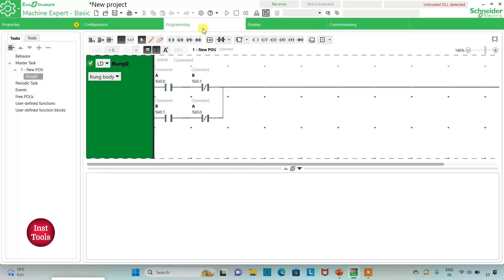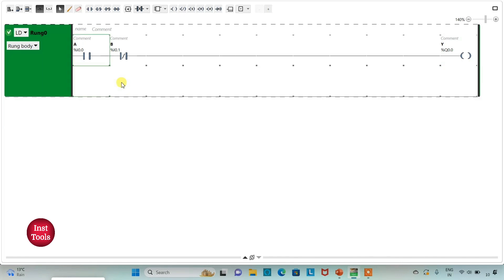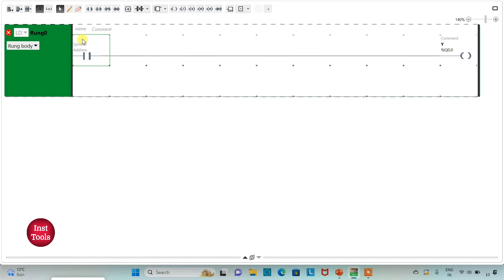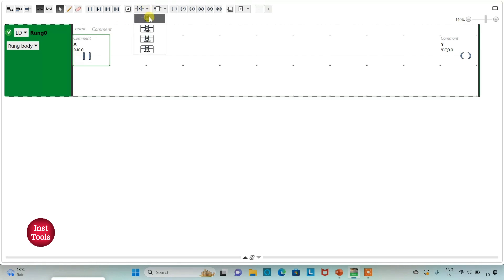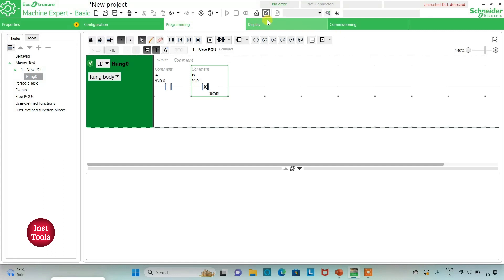I will exit full screen, stop the simulator, go to Programming, and click full screen again. I will delete the existing contacts and implement XOR gate in only one line. I will insert a normally open contact and assign address I0.0 (symbol A), then insert the XOR function and assign address I0.1 (symbol B). For output Y to be on, either A or B should be on while the other is off.